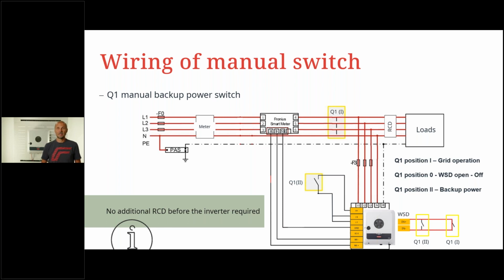And on the other hand, we also need to switch off the inverter in position 0. That means we have 2 closing contacts. One from position 1 and one from position 2, which are connected in the wired shutdown pin. So wherever you are, if position 1 or 2 is closed, the inverter can run. If this is open in position 0, the inverter will immediately stop and interrupt the production. So make sure you don't forget this, because otherwise you could have 2 voltages together, from the grid and as well from the inverter.